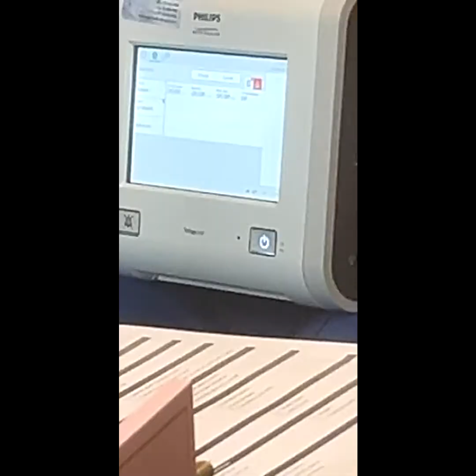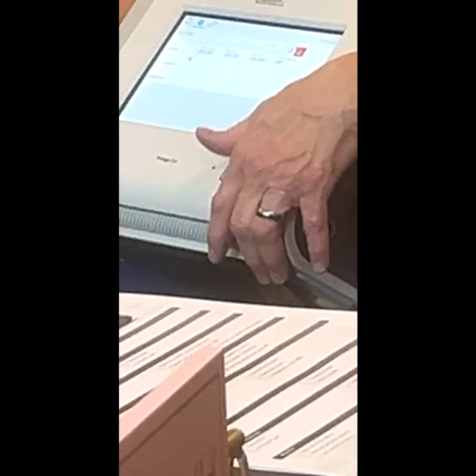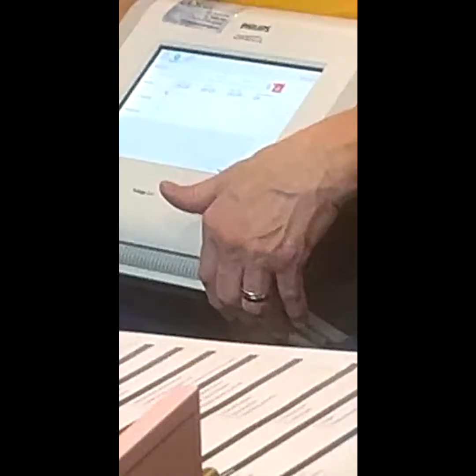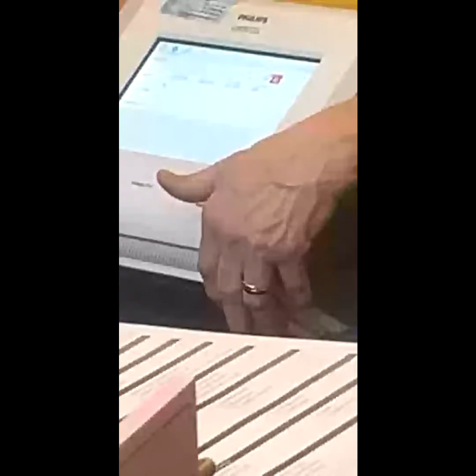If they can't exhale out or inhale in, they're going to retract and you're going to start seeing numbers go crazy. All right? Questions so far? Nope. All righty. So whatever we do on those alarms, we always set a low and high respiratory rate alarm. Mainly low, because we don't have an apnea alarm set. All right? So we want to make sure that if they're not breathing, if they're not riding this vent at the respiratory rate that's set, then we know that they're not breathing and it's going to alarm low respiratory rate. To me, it's an alarm, because you're not waiting 20 seconds or whatever.